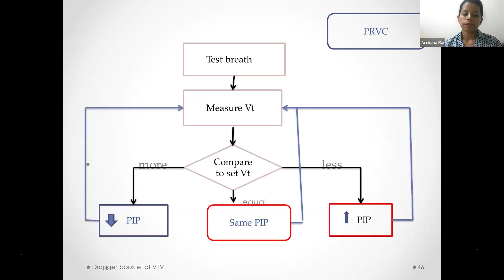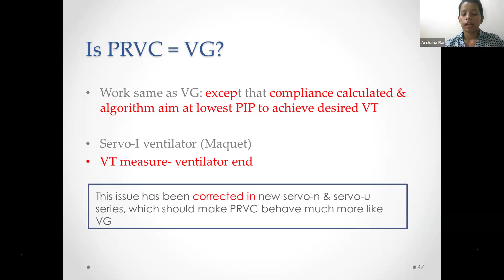So PRVC mode is there in the Servo-i ventilator, and in this the VT is measured at the ventilator end. This has been overcome in the new Servo ventilators like N and U, where it usually works like volume guarantee.